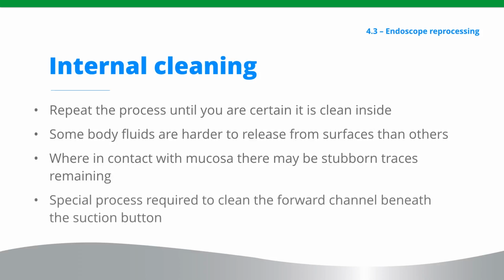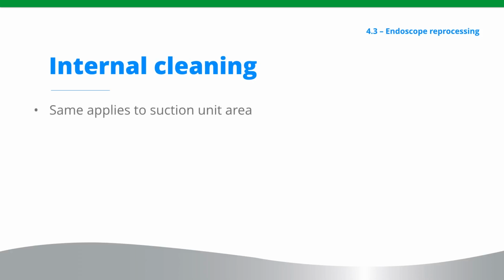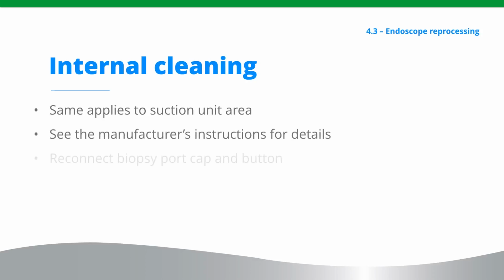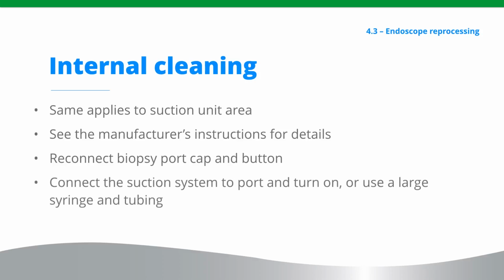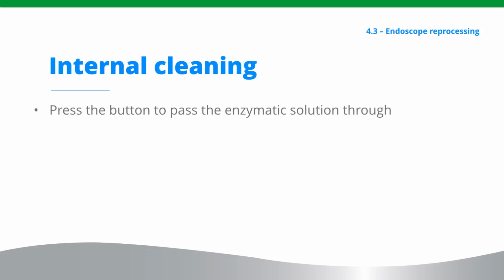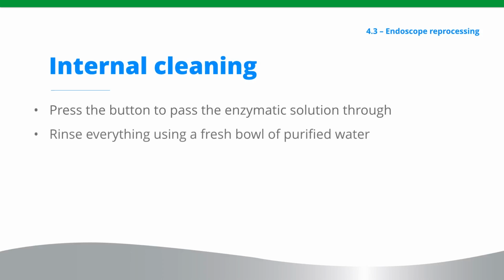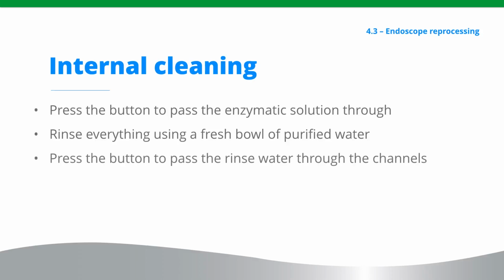A special process is required to brush clean the forward channel beneath the suction button. The same applies to the suction unit area. See the manufacturer's instructions for details. With the biopsy port cap and button reconnected, connect the suction system to its port and turn on, or use a large syringe and tubing. Press the button and pass the enzymatic solution through until the solution starts to fill the aspirator bottle or the syringe. Rinse everything using a fresh bowl of purified water. Press the button as before to pass the rinse water through the channels.